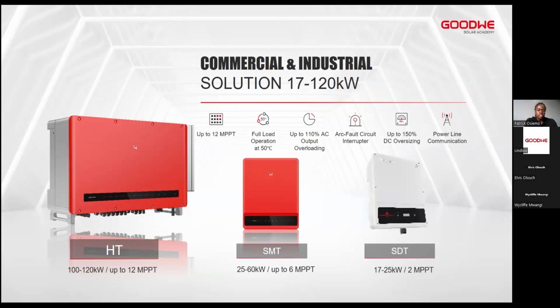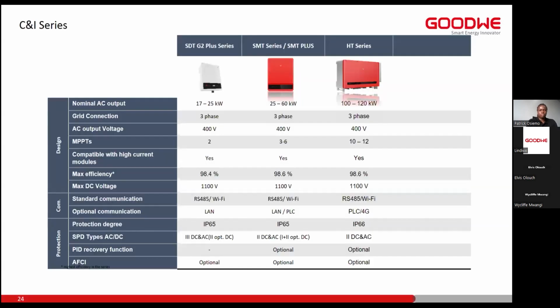And the power line communication is applicable to the big size rated inverter, that is the HT series. When you utilize the PLC or power line communication, you won't need to install the RS-485 communication, because the inverters will be communicating through the same AC cable that is outputting power from the inverter. So we do have a control system that will handle the power line communication.